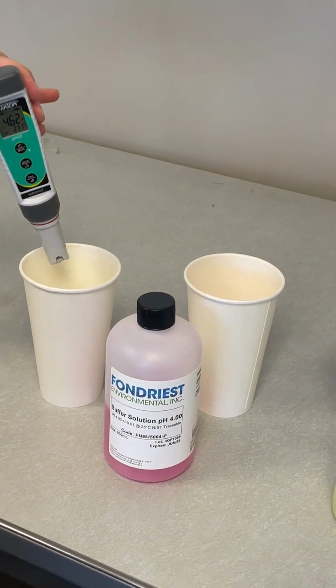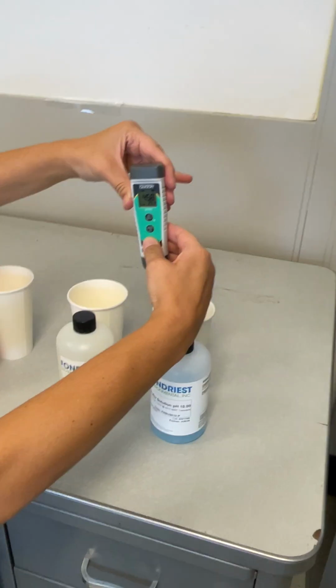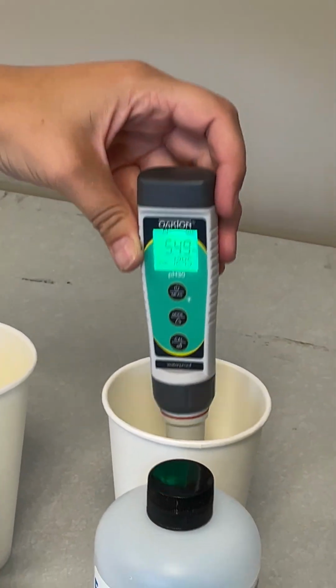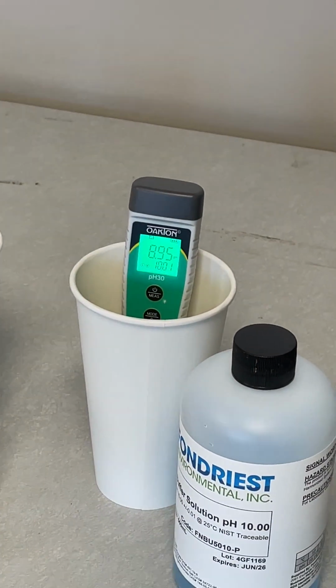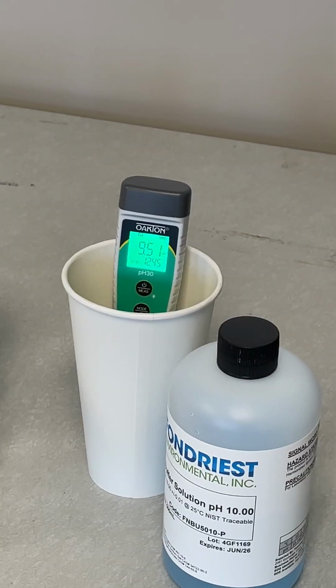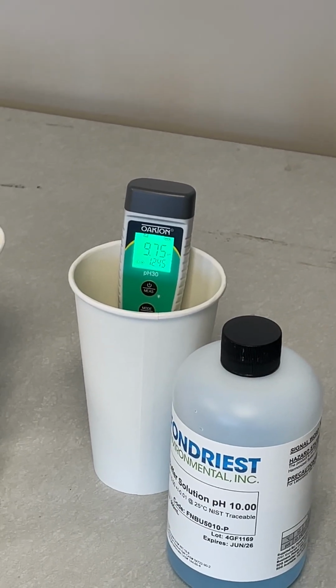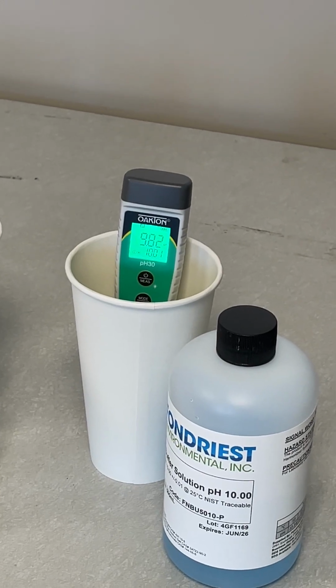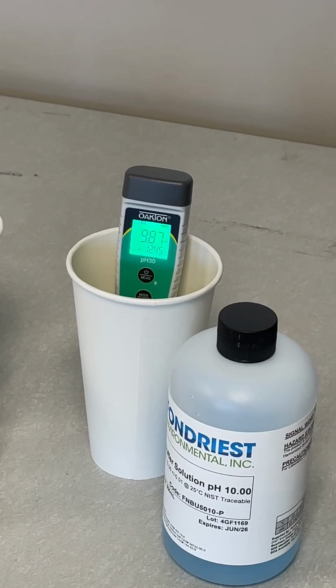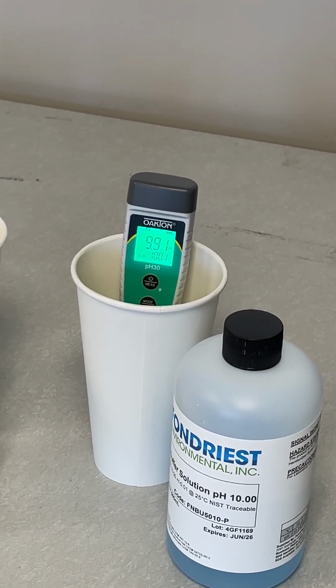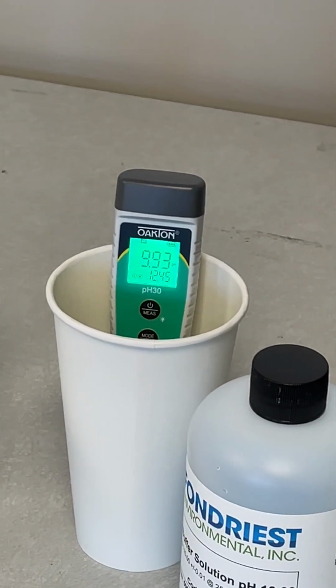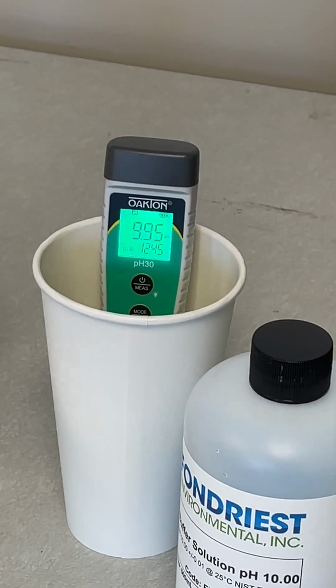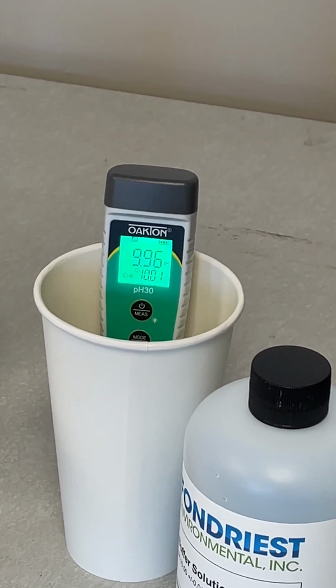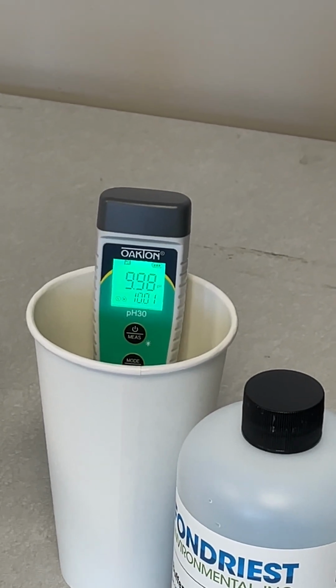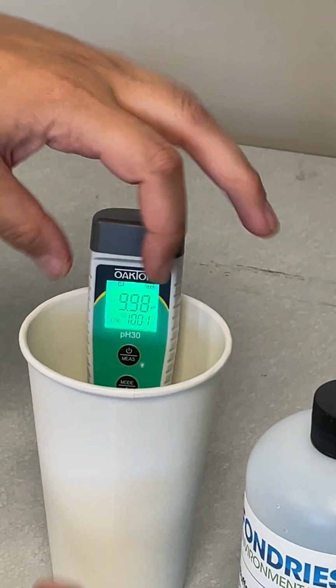And so then I'm gonna do the high point, which is the 10. So once again, long press calibrate until it turns on, it says calibrate. The numbers are gonna jump around all over again. But just like before, it'll figure it out eventually. It just takes time. Luckily, these ones are a little bit faster than our old ones, but they're still... and these will get you because sometimes the smiley face pops up and it goes away and pops up and it goes away. So you kind of gotta try to get it when the smiley face is there, and 10 is generally the hardest.